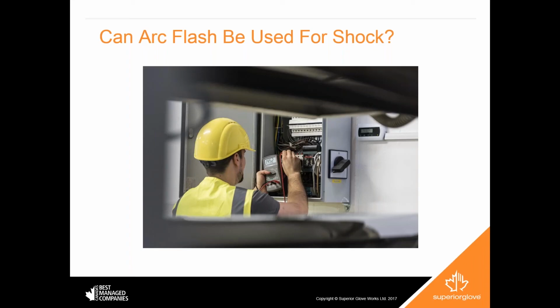So OSHA works with the National Fire Protection Association, and they created NFPA 70E, which is kind of the standard for regulations and for personal protective equipment. The standard that was developed by the Institute of Electrical and Electronics Engineers, the IEEE 1584, provides the method for calculating the incident energy of an arc flash event. So hopefully those help you. If you are looking for PPE, the best and most common standard to look for is the NFPA 70E.